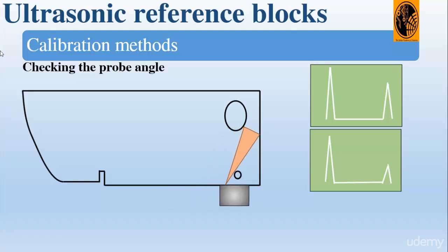The procedure can be repeated for 70 degrees, but reflecting energy from the plastic insert to produce a reliable signal is difficult. Therefore, we suggest using the 1.5 millimeter hole as a target instead.